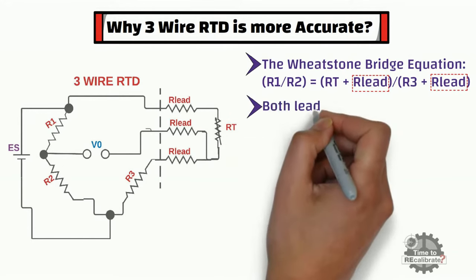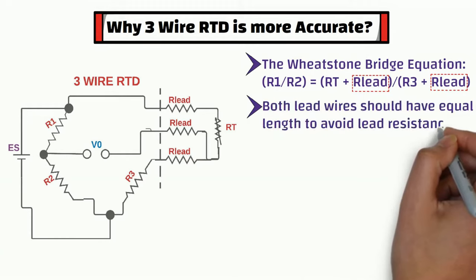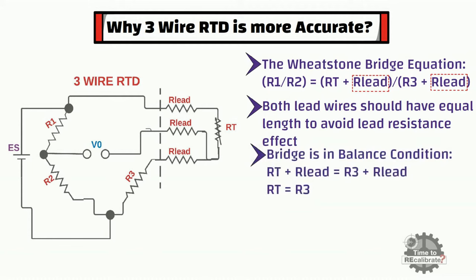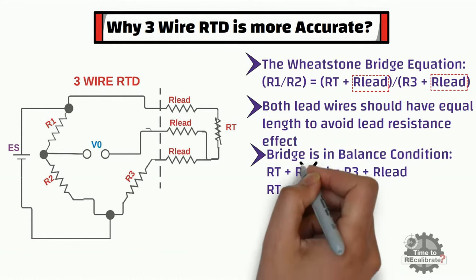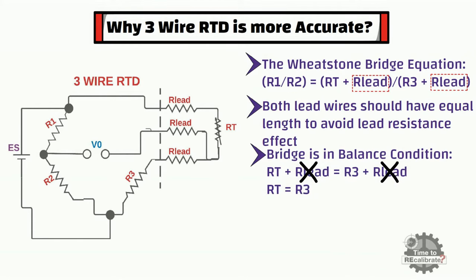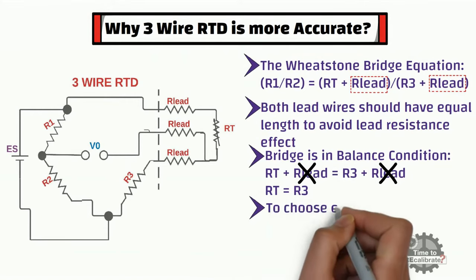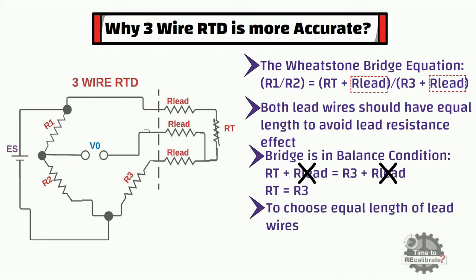However, both lead wires should have equal lengths to avoid any lead resistance effect in the circuit. As you can see, this is the equation when the Wheatstone bridge is in balance condition. In this equation, lead resistance cancels out with the help of the third lead wire, and this is the reason that temperature measurement does not get affected by lead resistance. However, great care needs to be taken to choose equal lengths of lead wires — if you do not choose equal length lead wires, temperature measurement error will occur.